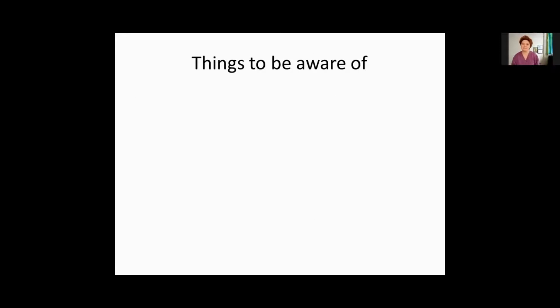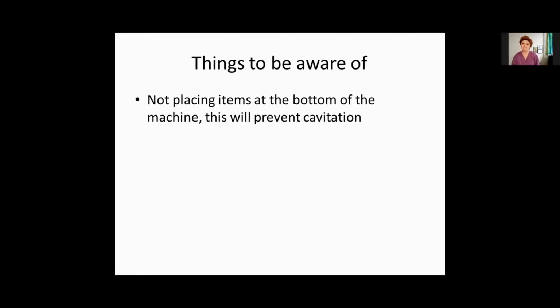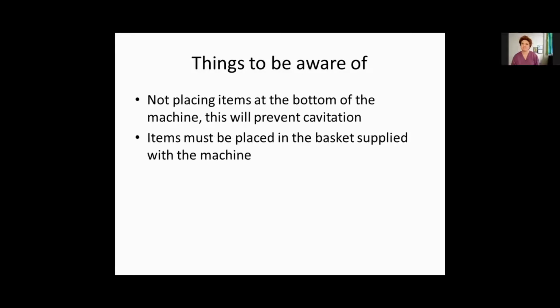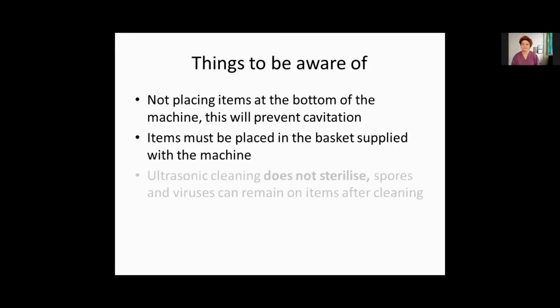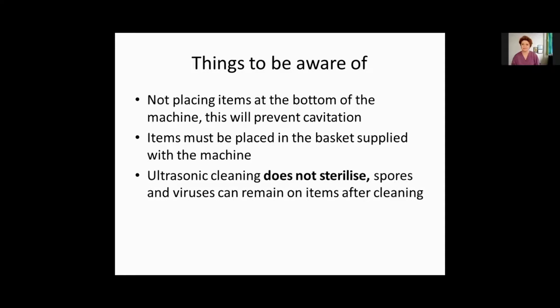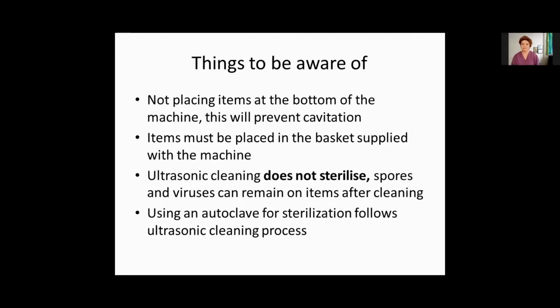Yeah. So things to be aware of: not placing items at the bottom of the machine, because this will prevent cavitation. Items must be placed in a basket supplied with the machine. Ultrasonic cleaning does not sterilize, so spores and viruses can remain on items after cleaning, and using an autoclave for sterilization follows an ultrasonic cleaning process.